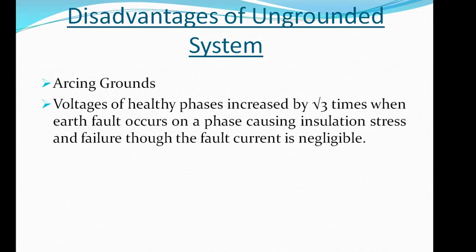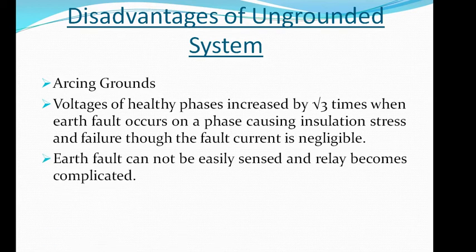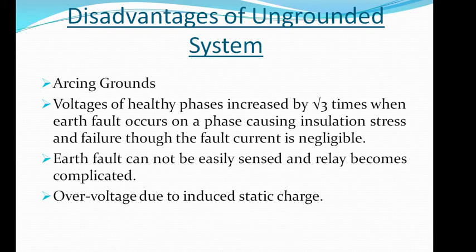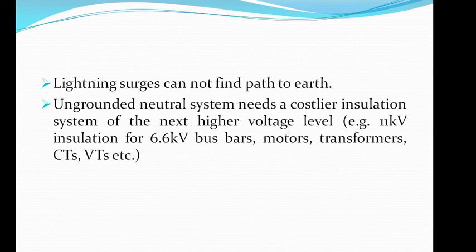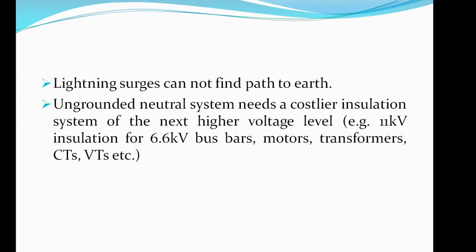Additionally, the voltages of healthy phases increase by root three times their normal values when an earth fault occurs on a phase, causing insulation stress and failure. Though the fault current is negligible, earth faults cannot be easily sensed, making design complicated. Overvoltages due to induced static charge are also a disadvantage of an ungrounded system, as lightning surges cannot find a path to earth to get discharged. Finally, an ungrounded neutral system needs a costlier insulation system of the next higher voltage level — for example, a 6.6 kV system must adopt 11 kV insulation design, demanding increased cost.